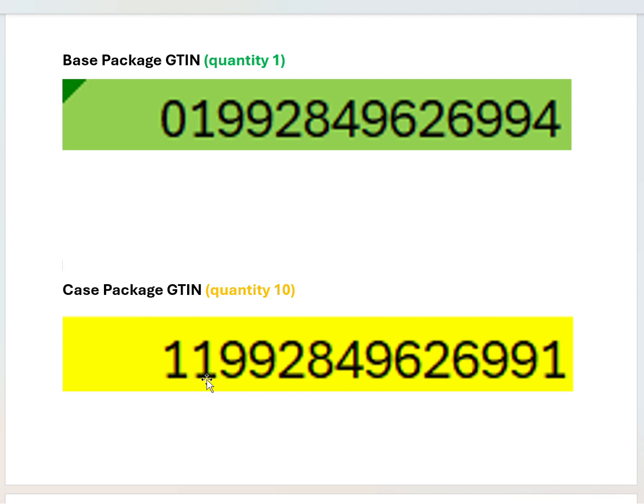Also, if you put this number in the FDA GUDID database, or even other databases such as UDI, Saudi has a database, China, South Korea, Taiwan, Australia, and it's registered, it's going to give that product information for the medical device. As we know, this is used for tracking and tracing purposes. It's used for reporting complaints against the product. It's even used for counterfeiting. Also, if you want to import products into the US, the import or customs organization will ask, what's the UDI? They'll look for that UDI, unique device identifier.